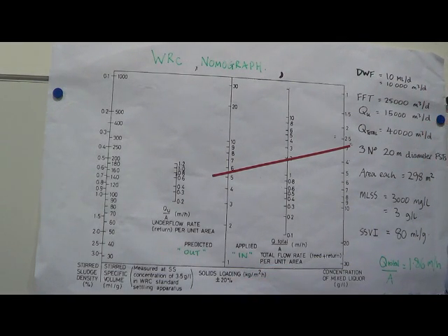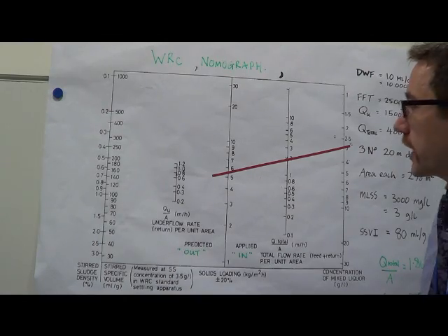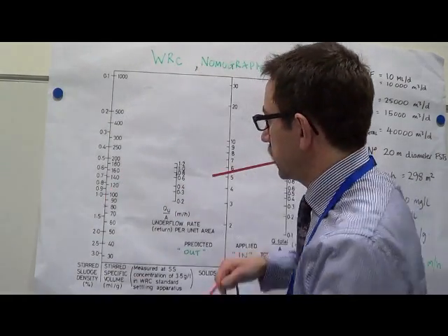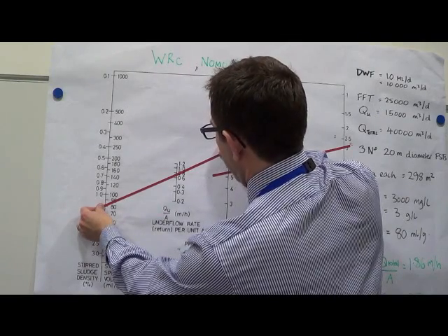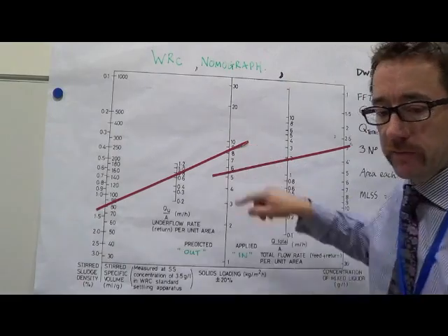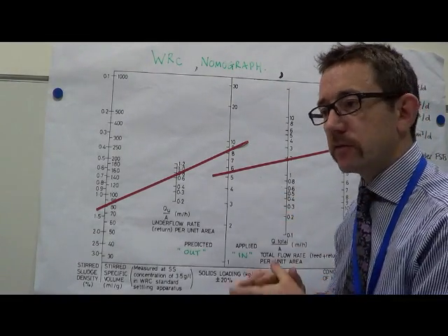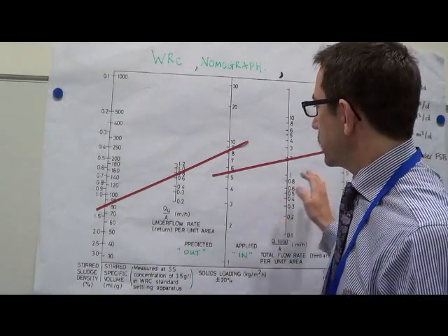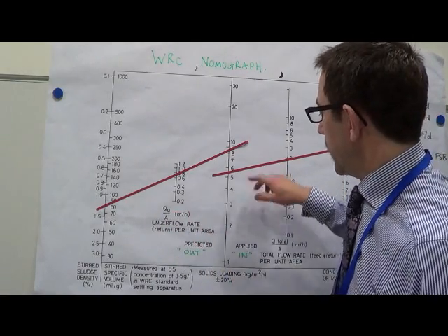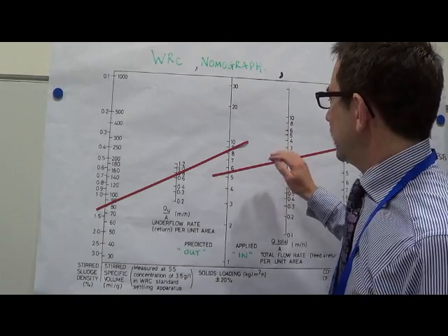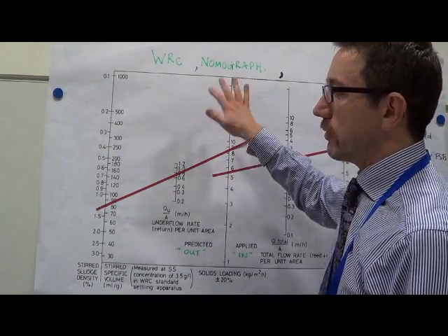So what is my tank capable of doing? Well, its SSVI is 80, we said, so that's one of my dots. So I'll do a dot there. I've said that the underflow velocity divided by area is 0.7, so it's capable of getting rid of about 8.5. Happy days, right? So in these normal circumstances, my tank will be fine, because although there's a bit of plus or minus on this calculation, that's saying I'm putting less onto my tank than it's capable of taking out.